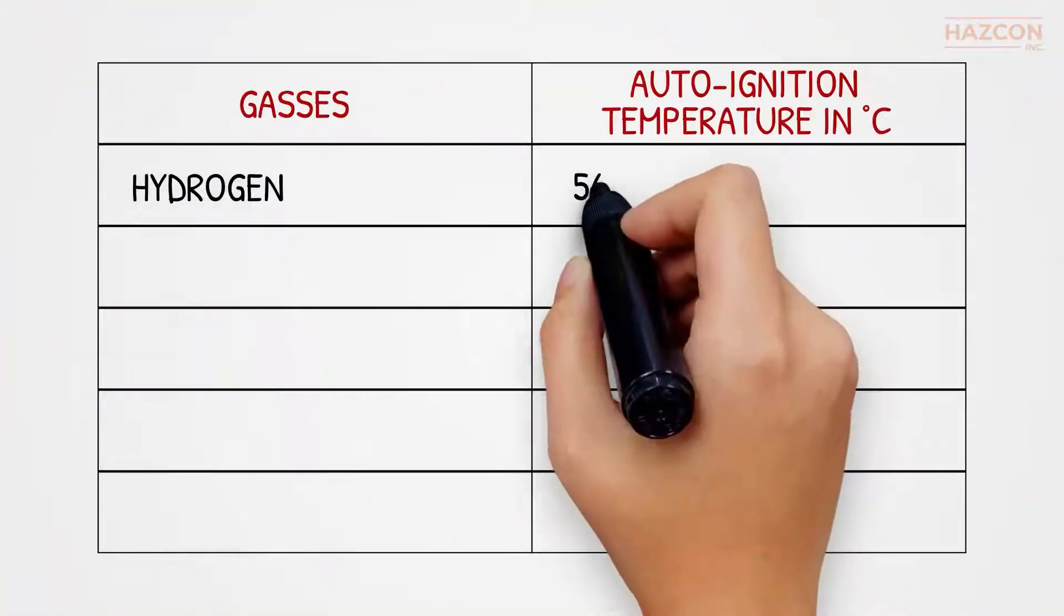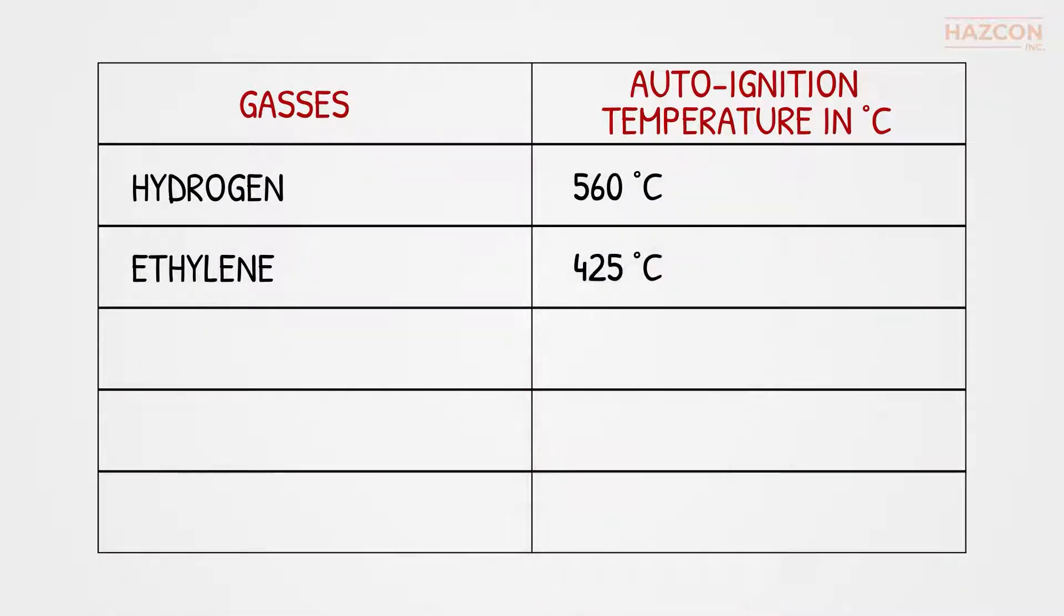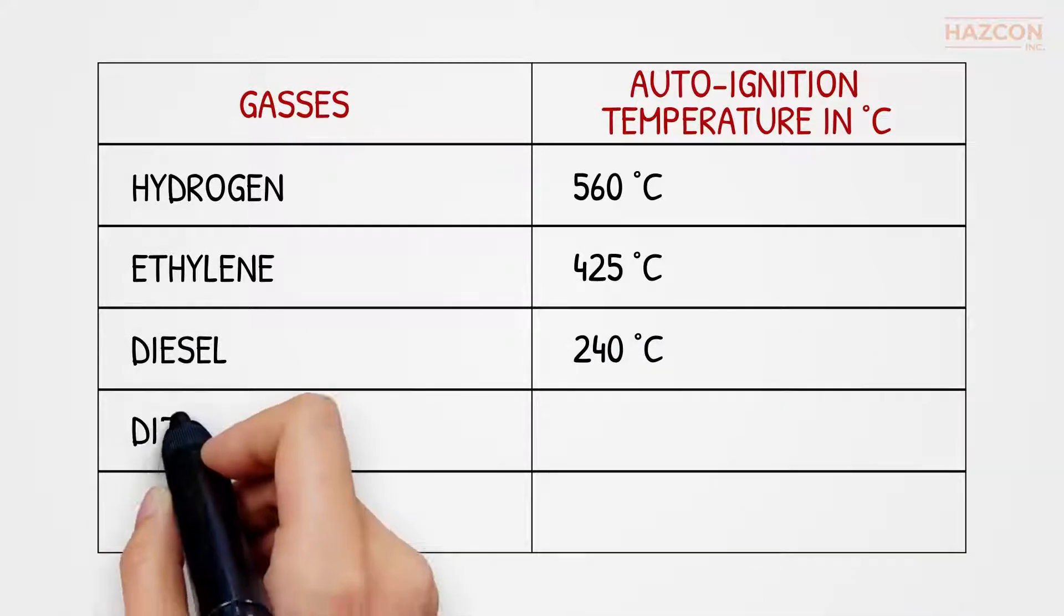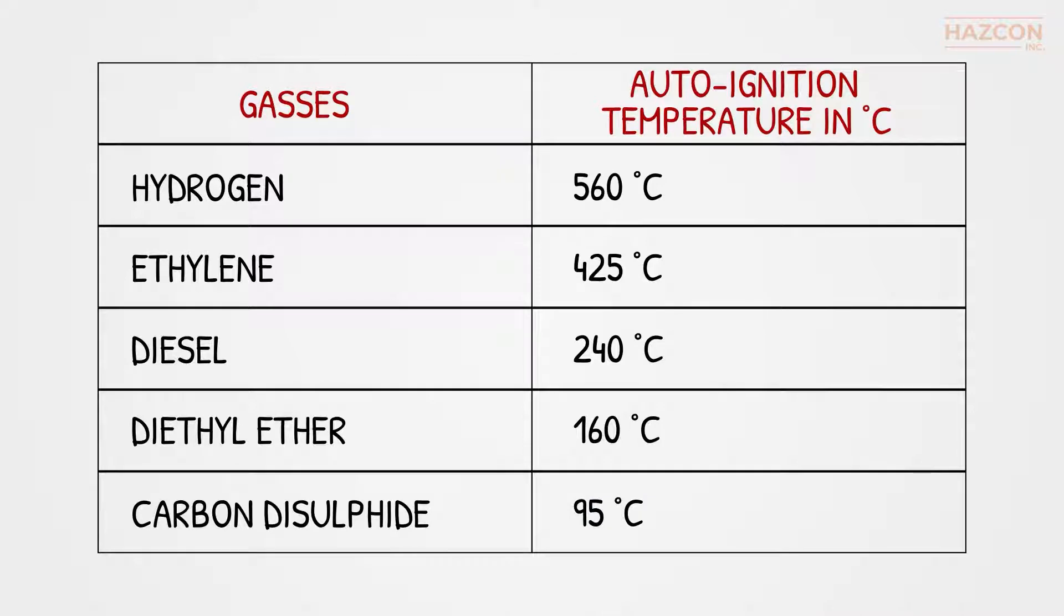For instance, hydrogen has an auto-ignition temperature of 560 degrees Celsius, ethylene 425, diesel 240, diethyl ether 160, and carbon disulfide has 95 degrees Celsius.